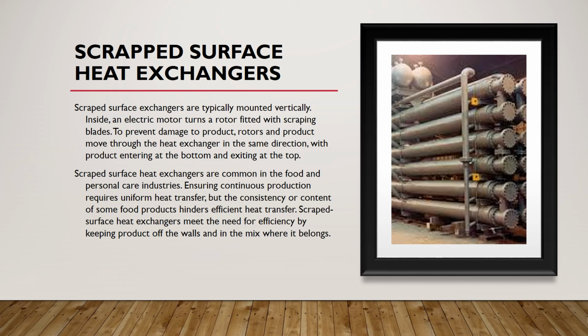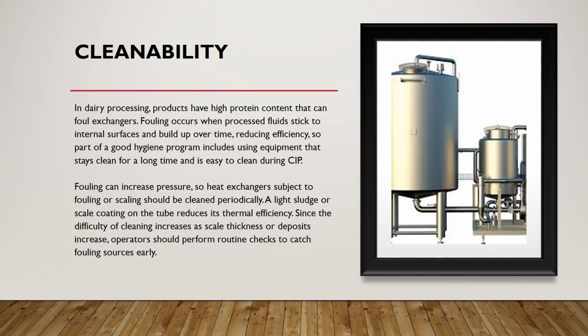Ensuring continuous production requires uniform heat transfer, but the consistency or content of some food products hinders efficient heat transfer. Scraped surface heat exchangers meet the need for efficiency by keeping product off the walls and in the mix where it belongs. In dairy processing, products have high protein content that can foul exchangers. Fouling occurs when processed fluids stick to internal surfaces and build up over time, reducing efficiency. So part of a good hygiene program includes using equipment that stays clean for a long time and is easy to clean during cleaning cycles.